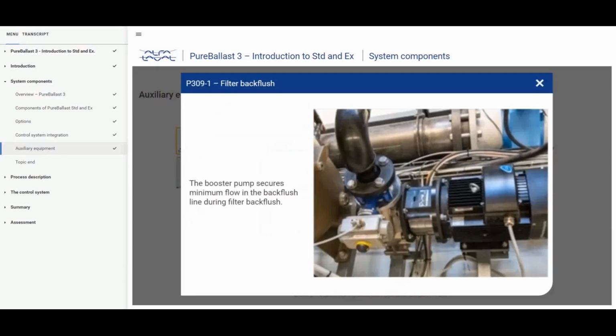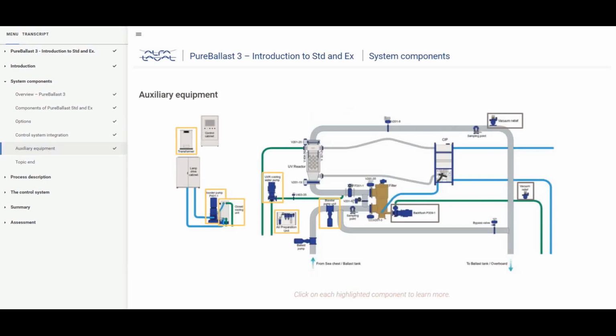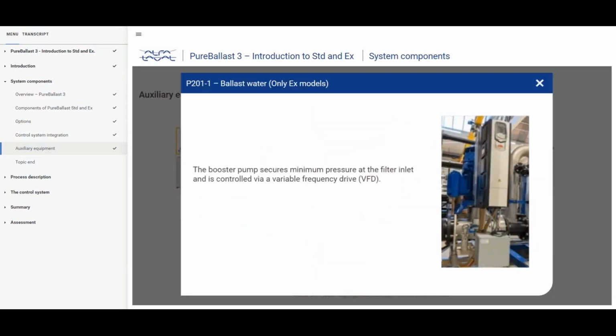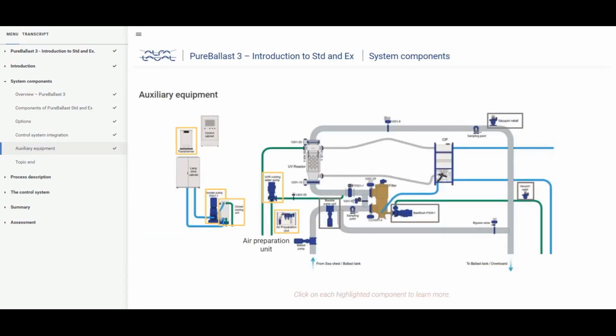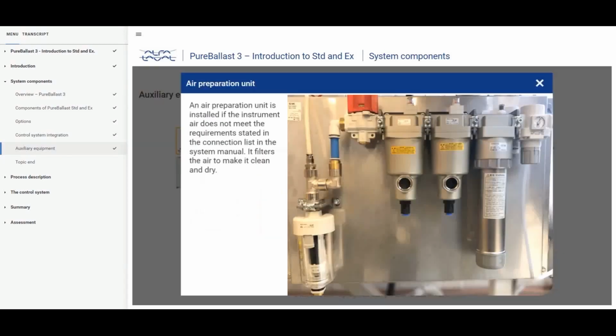The booster pump secures minimum flow in the backflush line during filter backflush. The booster pump secures minimum pressure at the filter inlet and is controlled via a variable frequency drive, VFD. An air preparation unit is installed if the instrument air does not meet the requirements stated in the connection list in the system manual. It filters the air to make it clean and dry.